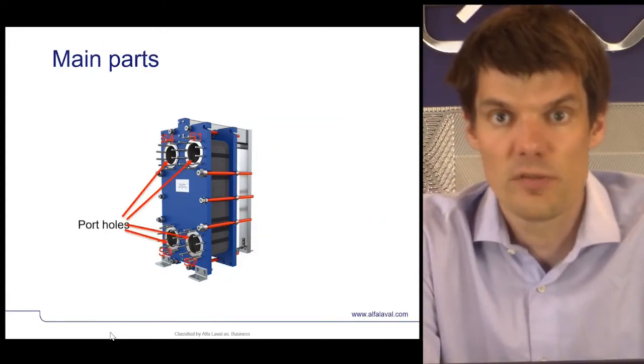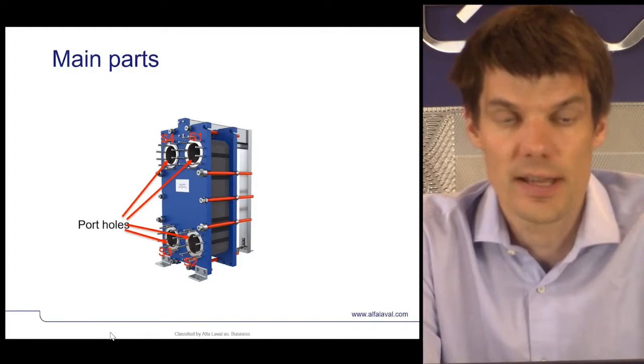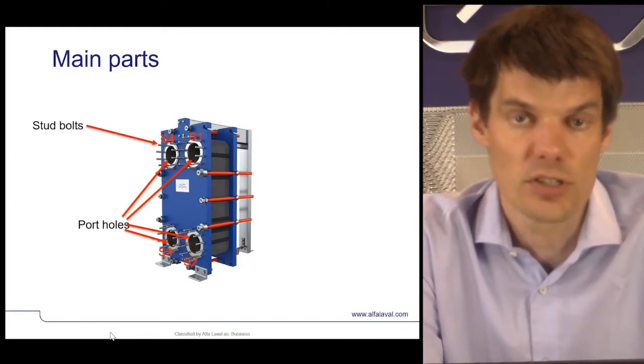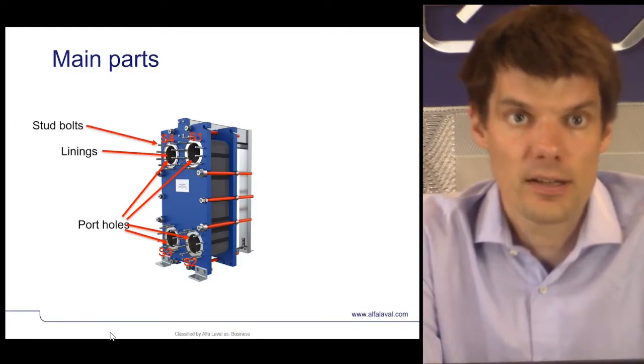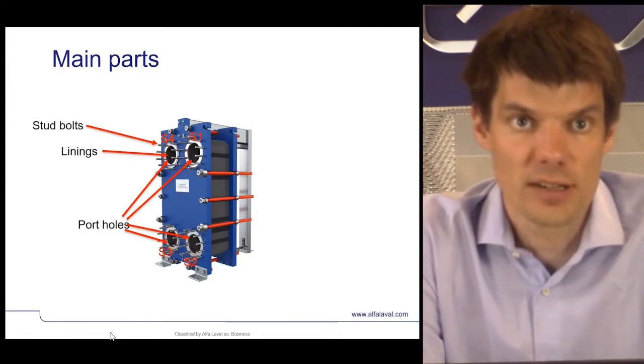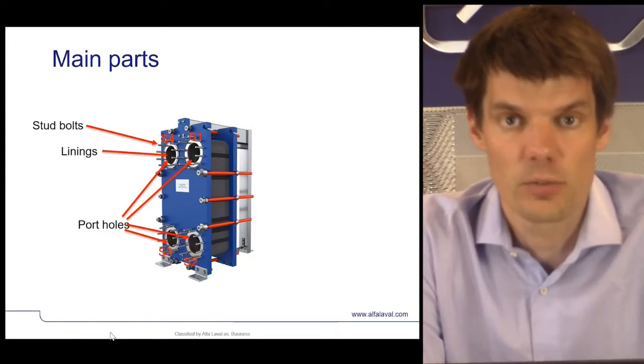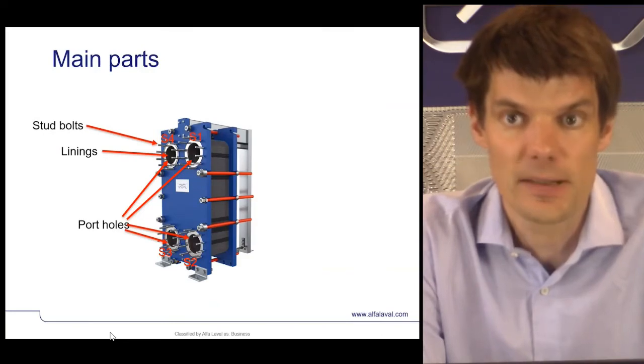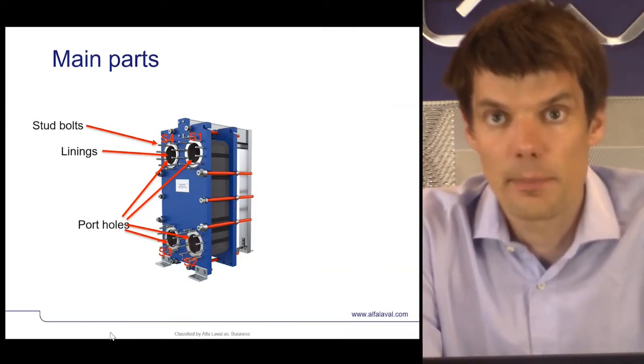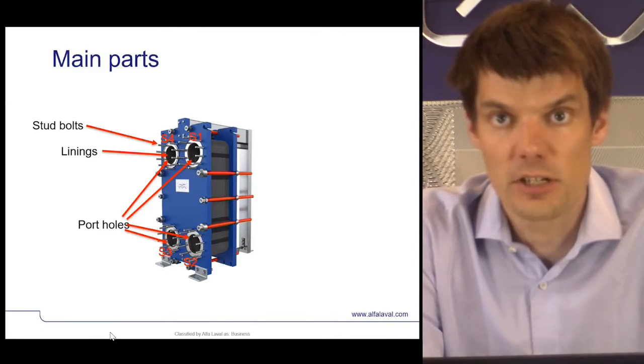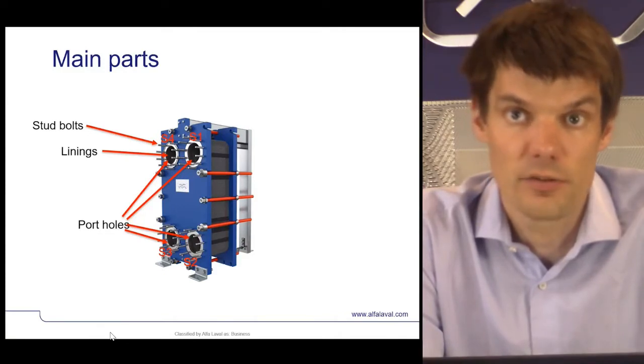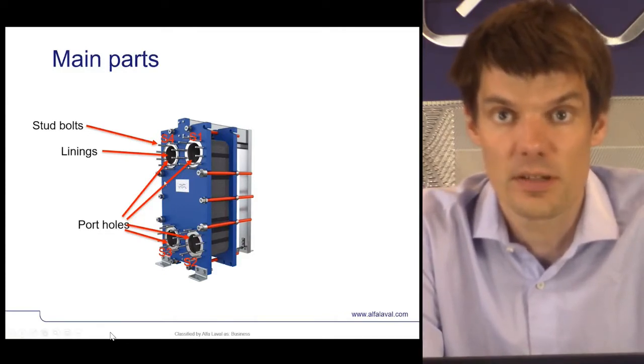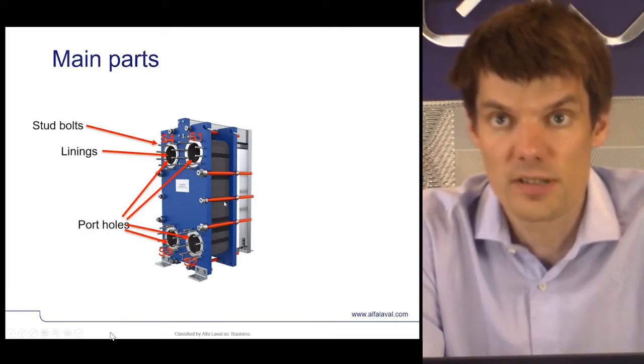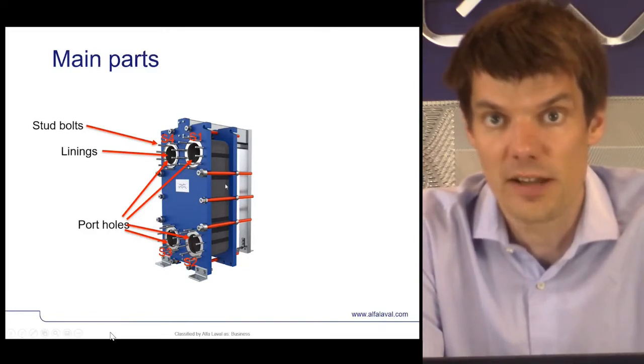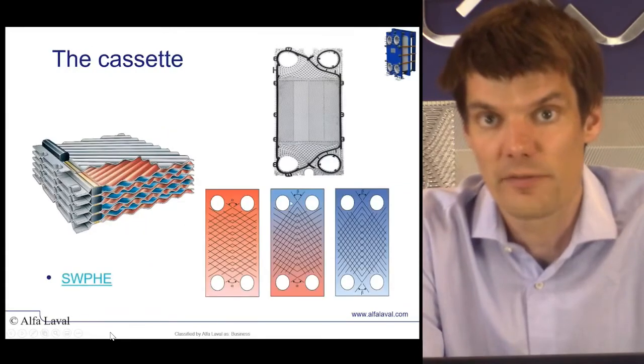On the frame plate, you will find the ports as well as stud bolts and linings, which make sure that the incoming fluid doesn't get in contact with the carbon steel frame plate. The semi-welded is built up like the traditional plate and frame heat exchanger with plates, which could be of either 316, 304 or titanium material. The plates are pressed so that when they are stacked together, they form a channel with a very efficient thermal conductivity pattern, always giving turbulent flow.